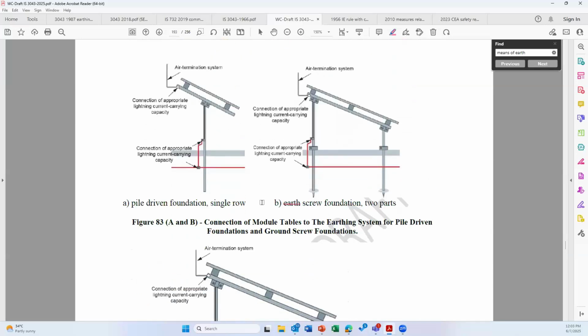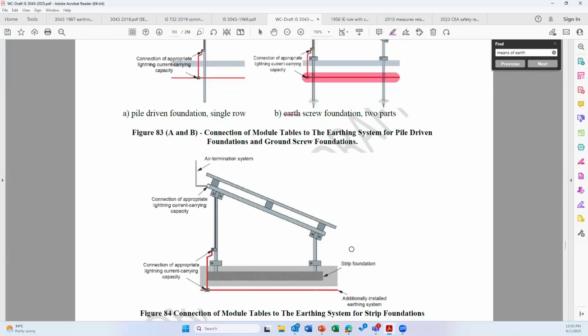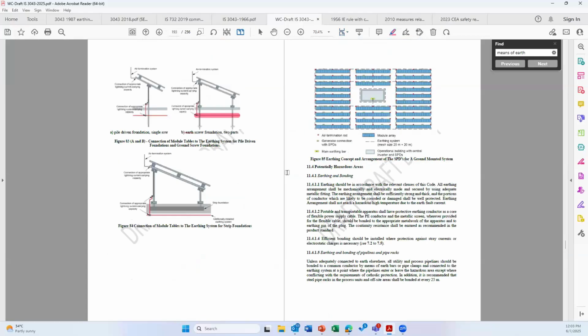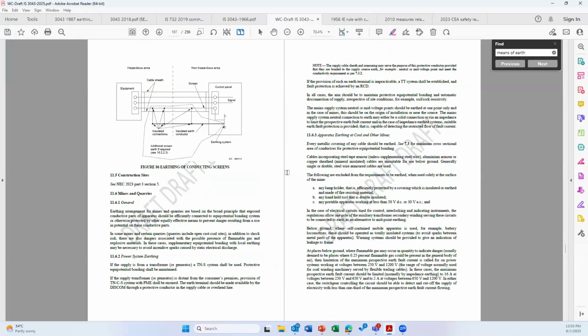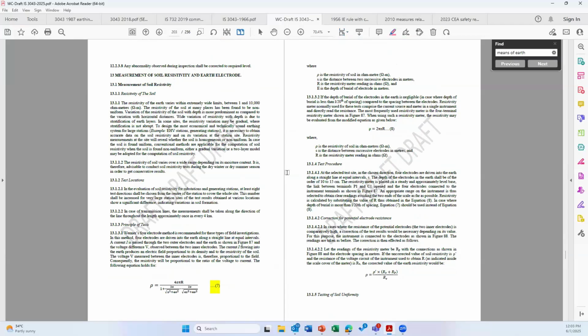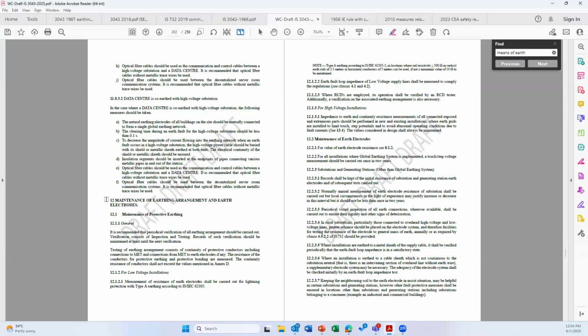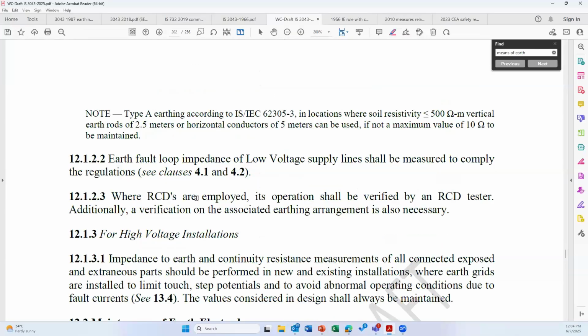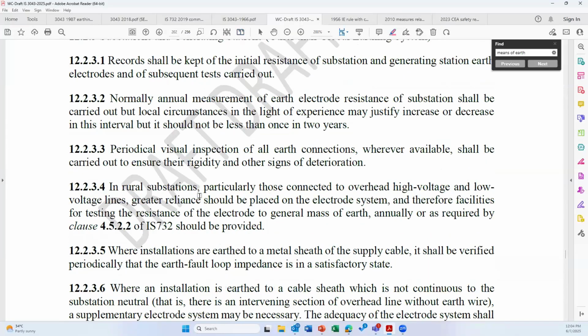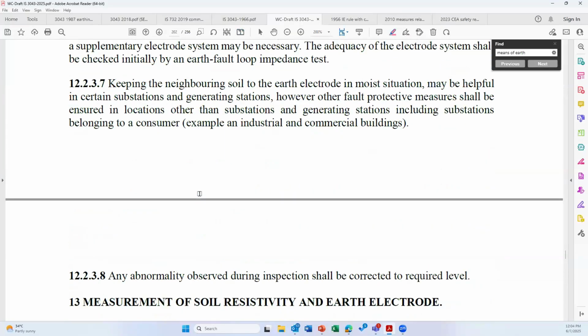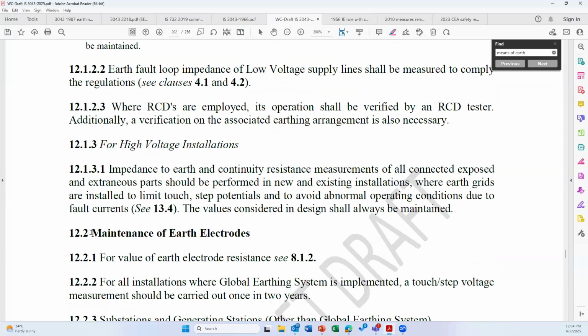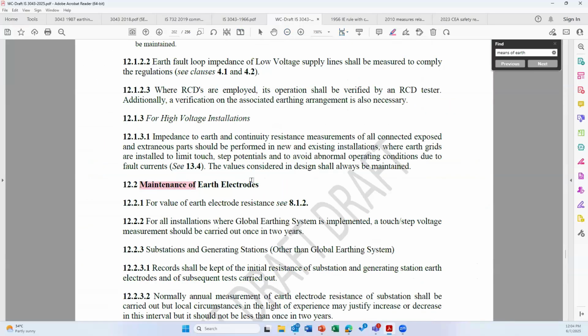Similarly, how to earth in case of a floor-mounted solar PV installation. So this is the additional information. Similarly, the next chapter, chapter 12, talks about the maintenance of earthing arrangement and earth electrode. Here, you can find some information on how to maintain the earth electrode and how to maintain the protective equipotential bonding.